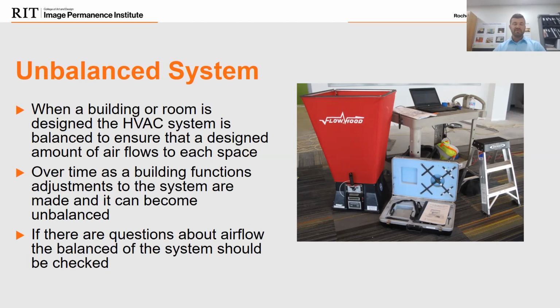So making sure a system is balanced matters, and there's no real set rule like I should balance it every 4 or 5 years. If you move rooms a lot, or adjust spaces and collection spaces a lot, you should definitely consider balancing. If you're changing use, or moving gallery walls, you might want to consider balancing that system, because over time, as we change uses, functions, and even employees, different employees will put different settings or components, and that changes the balance of that system. It can throw things out of whack.